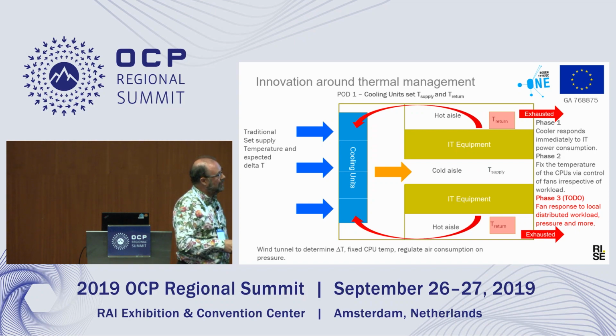But really what I'm going to focus on today is this phase 2, where we've taken control of the CPU fans. Again, we've gone back to our wind tunnel and we said we want the CPU to run at 75 centigrade all the time, irrespective of the workload. And that will give us a constant delta T, which the cooling units can synchronize to. To do that, we need to take control of the fans and change the fan speed so that the maximum CPU temperature is maintained.